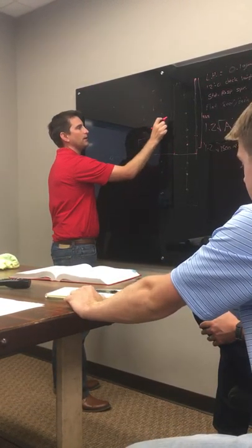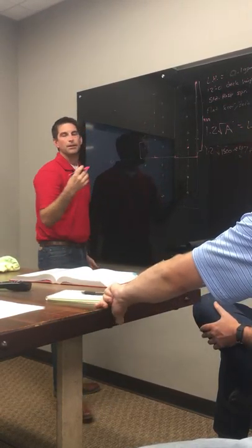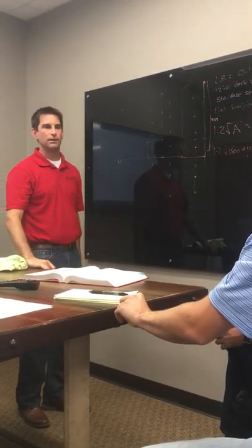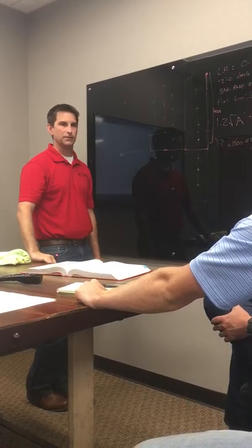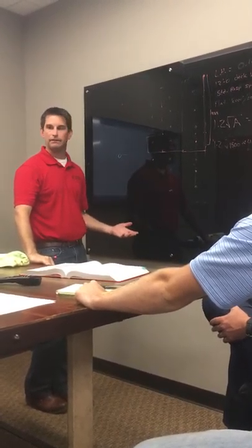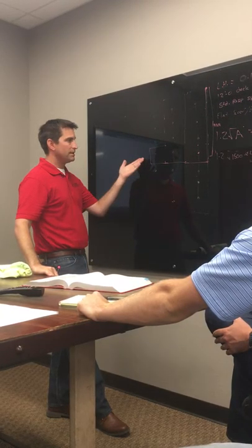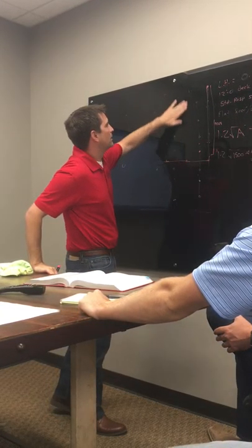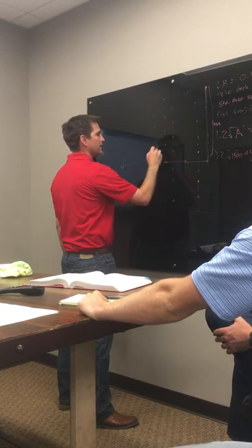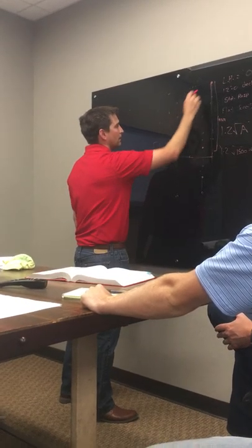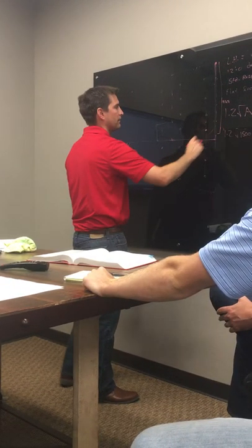Until you get to a point where you got your 1500 or maybe a little over 1500. You can go over. You don't want to go bigger than you have to. So we just keep doing that until we get there. That's it. That's all you gotta do. It's that simple. So now when I do this calculation, it's gonna include all of those sprinklers flowing.